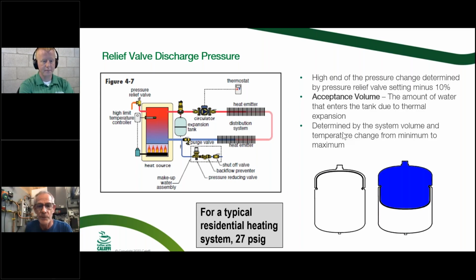And yeah, here we came up with, we would suggest 27 psi. I know the relief valves, a relief valve that's rated at 30 psi, my understanding is it should be able to go up to 30 and then start to weep or trickle a little bit. It's not going to pop full off at 30 psi. So if you stay at 27, you're below that threshold where you maybe get a little seeping, assuming that it's made accurately with the spring tension.